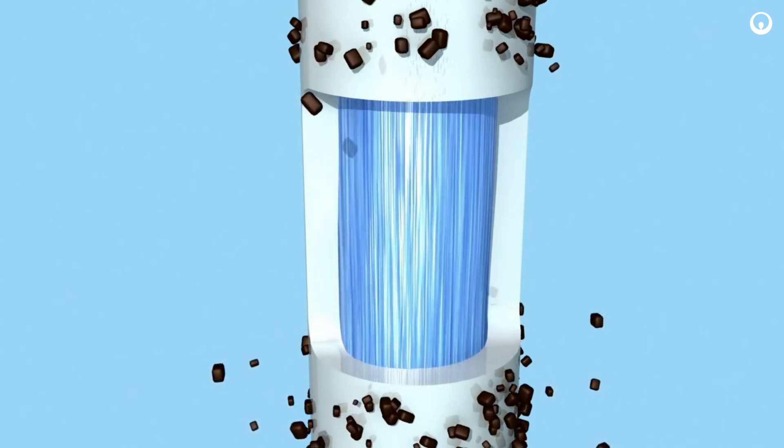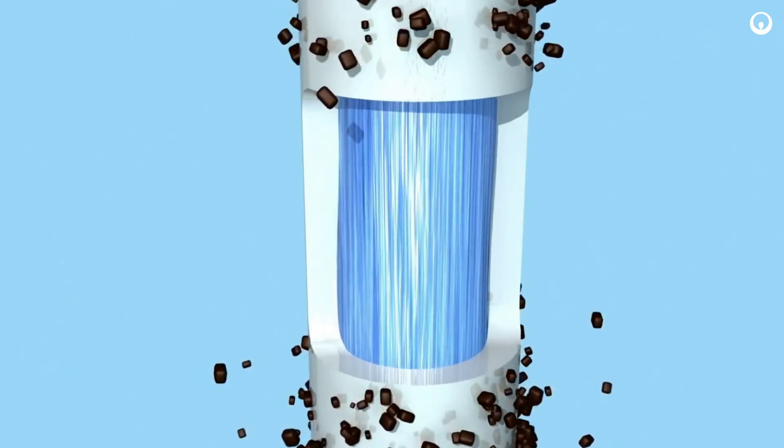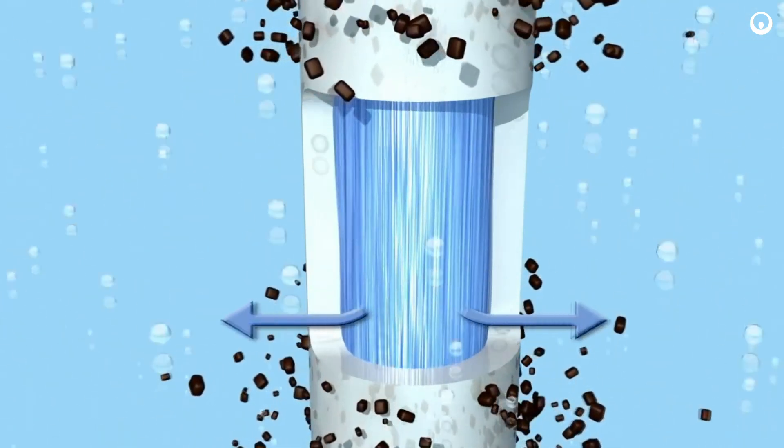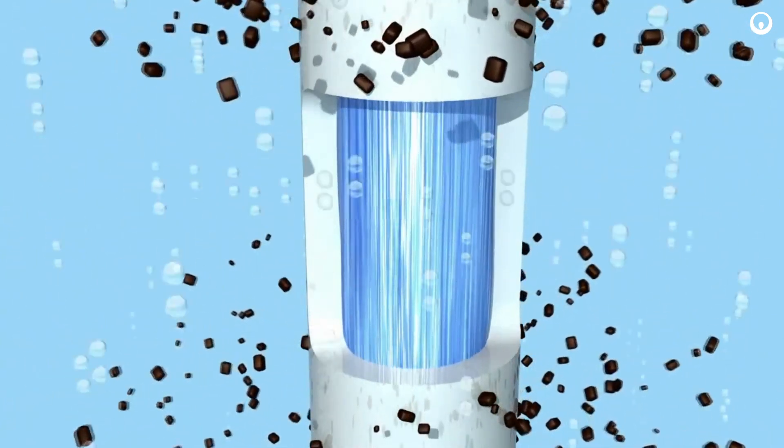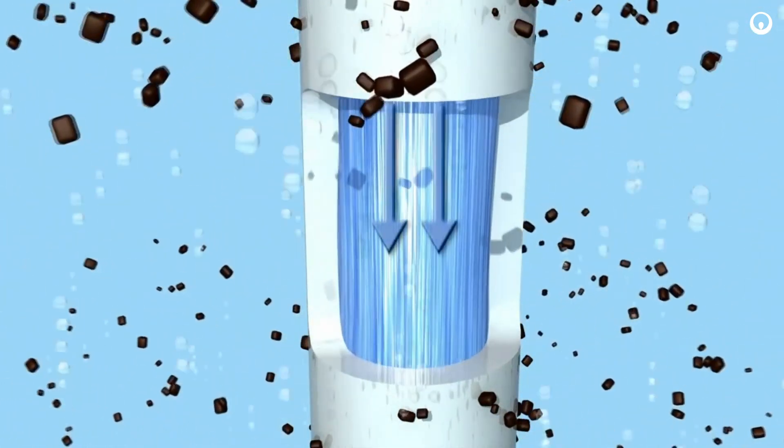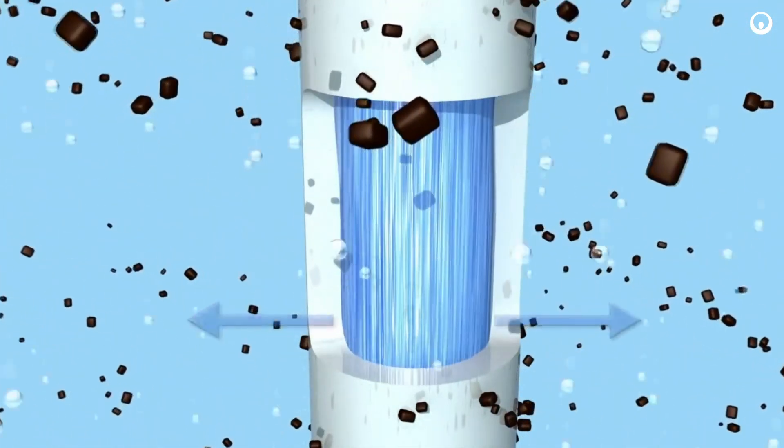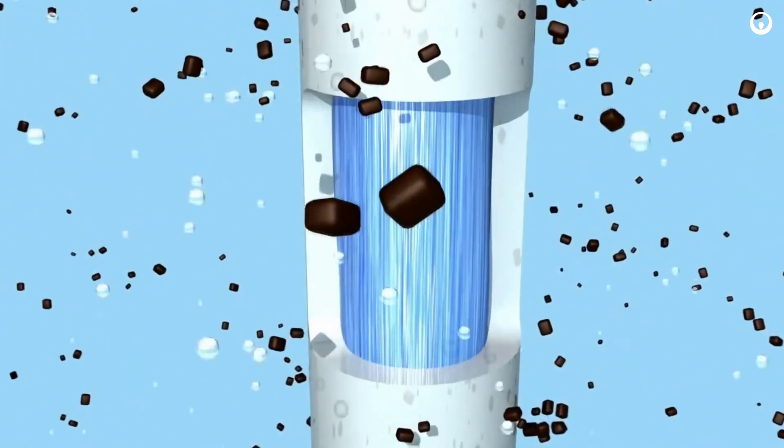Periodically, filtrate flow will be reversed in a backwash operation to dislodge particles from the membrane surface. During backwash, aeration is initiated to keep the particles in suspension and the membrane tanks are drained to discharge the concentrated water.